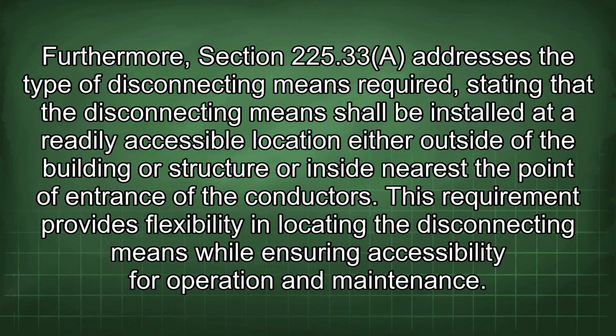Furthermore, Section 225.33 addresses the type of disconnecting means required, stating that the disconnecting means shall be installed at a readily accessible location either outside of the building or structure or inside nearest the point of entrance of the conductors. This requirement provides flexibility in locating the disconnecting means while ensuring accessibility for operation and maintenance.